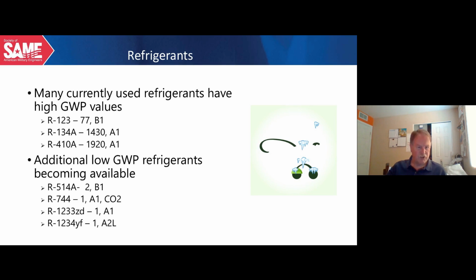R134A is a medium pressure refrigerant. It has a global warming potential of 1,430, and it has a safety group classification of A1. And then last but not least, R410, which is a high pressure refrigerant used in residential and unitary type equipment, has a global warming potential of 1,920 and is also a safety classification of A1 refrigerant.